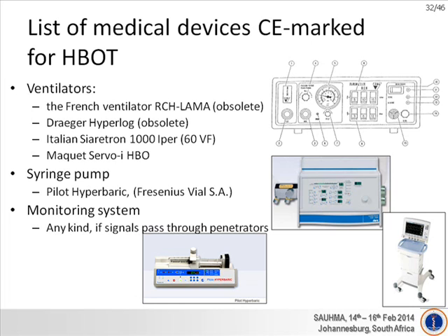And the problem is that nowadays only a few devices in Europe are CE marked and allowed to go inside the hyperbaric chamber. Namely, this is the very old French ventilator Lama, which is obsolete and should not be used. This is only for historical purposes.